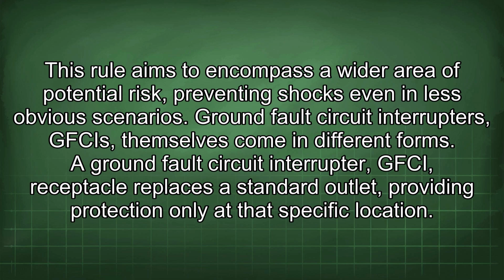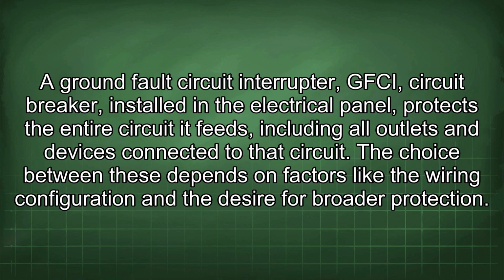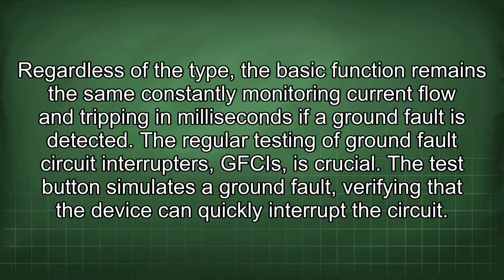GFCIs themselves come in different forms. A GFCI receptacle replaces a standard outlet, providing protection only at that specific location. A GFCI circuit breaker installed in the electrical panel protects the entire circuit it feeds, including all outlets and devices connected to that circuit. A choice between these depends on factors like the wiring configuration and the desire for broader protection. Regardless of the type, the basic function remains the same, constantly monitoring current flow and tripping in milliseconds if a ground fault is detected. The regular testing of GFCIs is crucial.